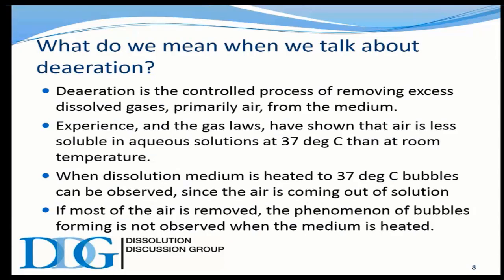So this is where it degasses and forms bubbles within the media, which, as we mentioned previously, are quite an impediment to proper dissolution.